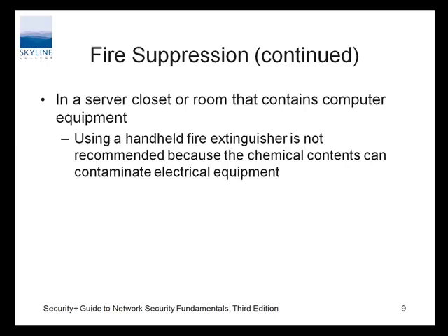Fire suppression for a server closet or room that contains computer equipment: handheld fire extinguishers are not recommended because of the dry chemical contents. I think this is another odd wording, because there are handheld CO2 extinguishers. That's what you would want to use in there. The handheld isn't a flooding system, so it's going to at least reduce the risk to you, the human. The flooding systems are the ones that really get you, where they just have a fire and flood the area, turn off the ventilation and flood the room with CO2.